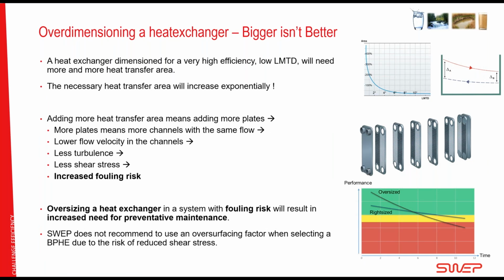There's another thing here. Many of you like very high thermal efficiency. So what do we mean by that? Well, one way of measuring thermal efficiency is LMTD, logarithmic mean temperature difference. And the lower the LMTD, the more energy you're extracting from the system, more energy efficiency, which is good, right? And brazed plate and plate and frame are really good at delivering energy efficiency. But when the requested LMTD is reduced, right? Squeeze more and more energy out of the system. The surface area needed will increase exponentially. It's not linear. It goes up very fast, right?